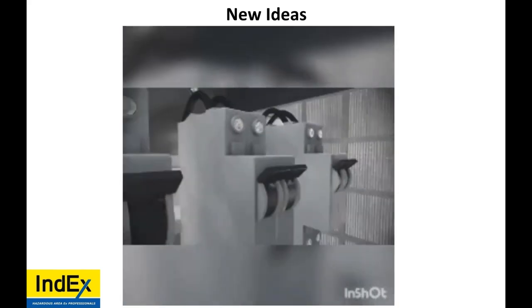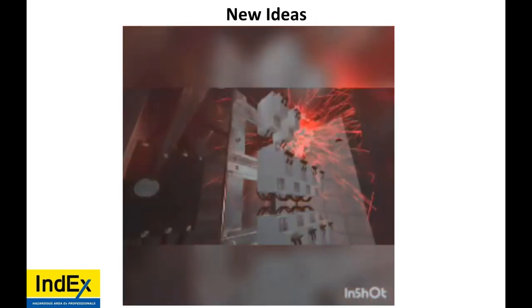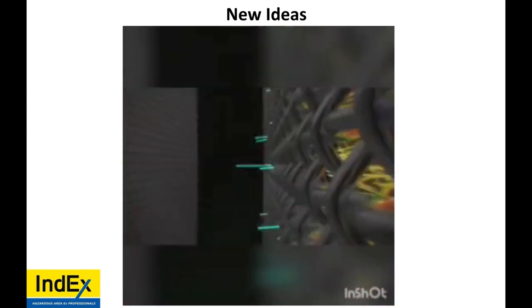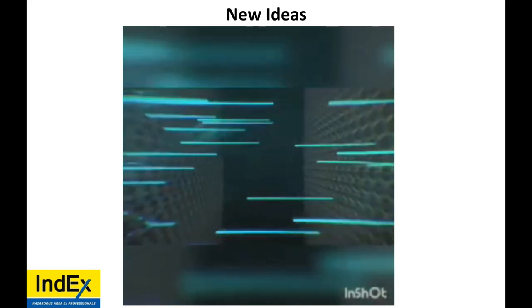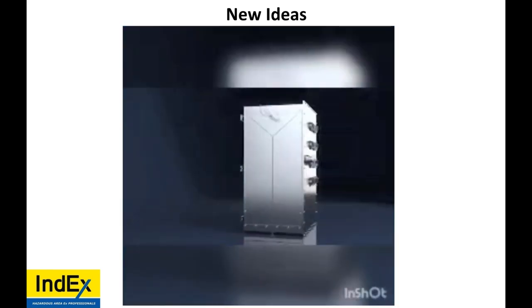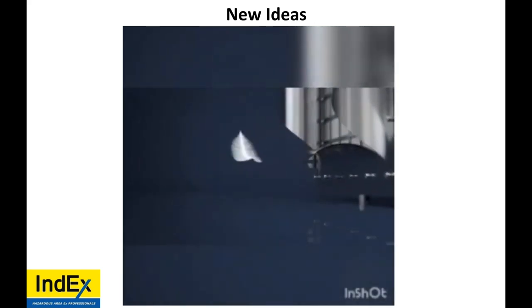So it's a good video to show that when there's an explosion inside, that heat, pressure, and particulate matter is stopped. The particulate matter is stopped by that mesh screen. And those screens cool down and slow down that explosive pressure. So it's 50% lighter than a traditional box. It's been approved by 2 ATEX notified bodies, with 30 patents pending. So I just wanted to give people an idea that there are new ideas.